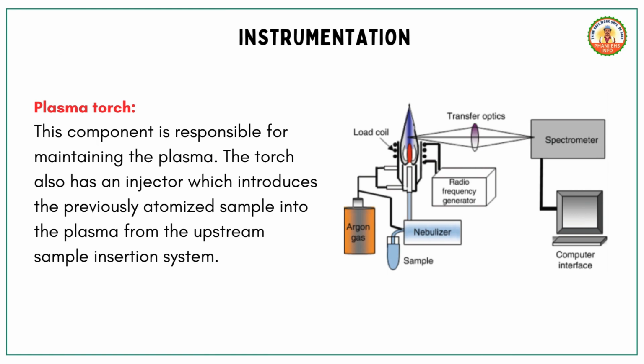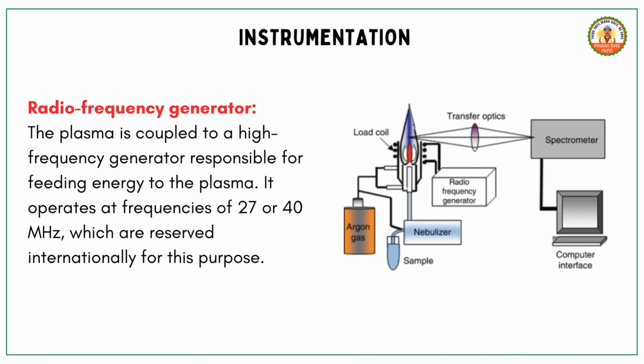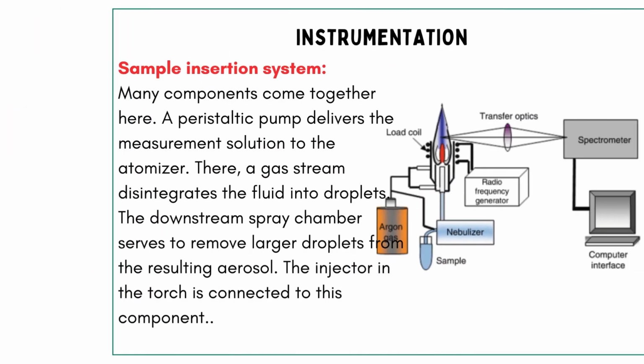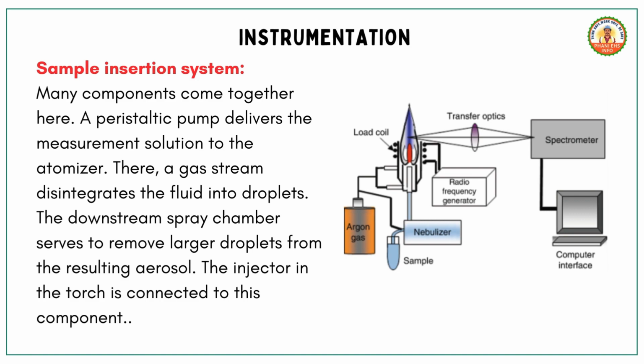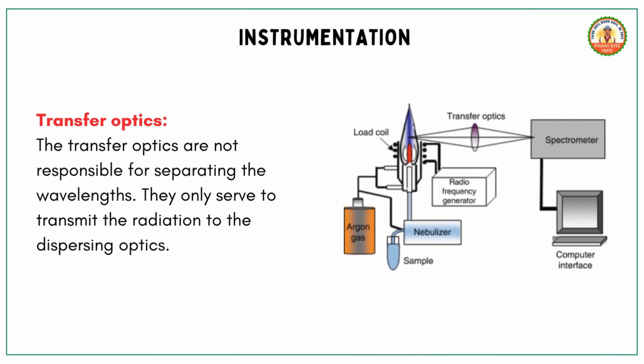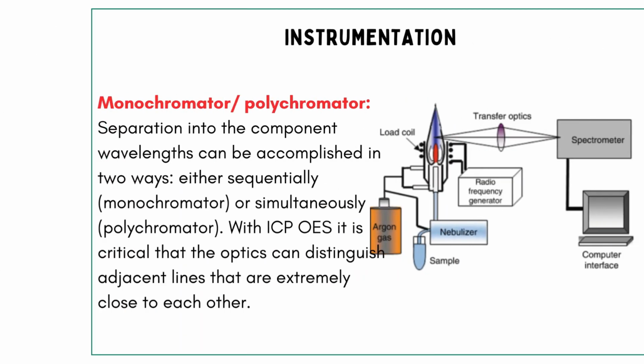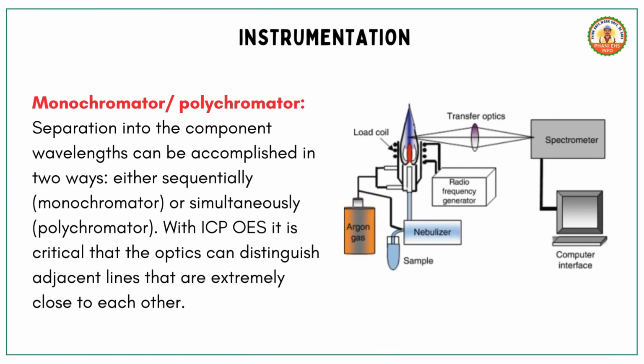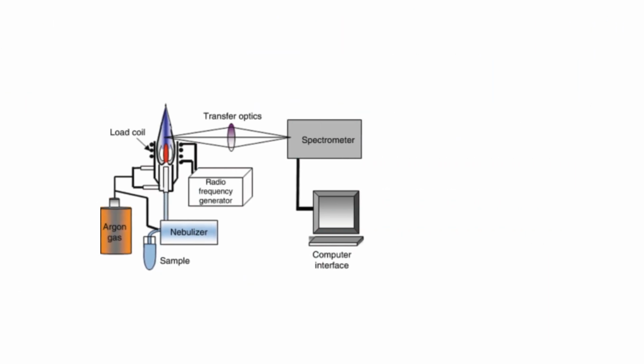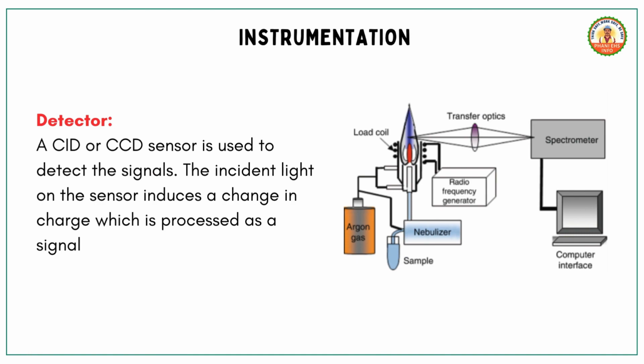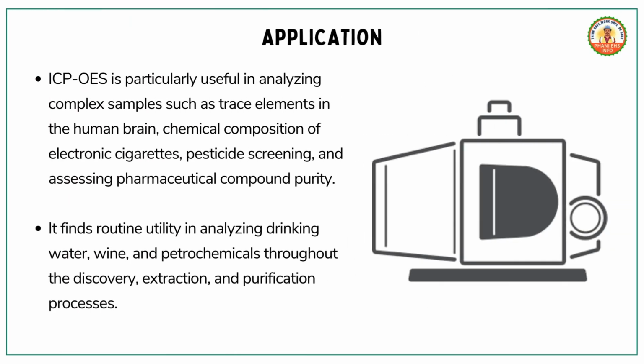Instrumentation. Plasma torch maintains the plasma and introduces the sample into the plasma using an injector. Radio frequency generator feeds energy to the plasma at frequencies of 27 or 40 MHz. Sample insertion system includes a peristaltic pump, atomizer, gas stream, and spray chamber to deliver and atomize the sample. Transfer optics transmit radiation to the dispersing optics. Monochromator polychromator separates wavelengths either sequentially or simultaneously to distinguish adjacent lines. Detector utilizes a CID or CCD sensor to detect emitted signals.